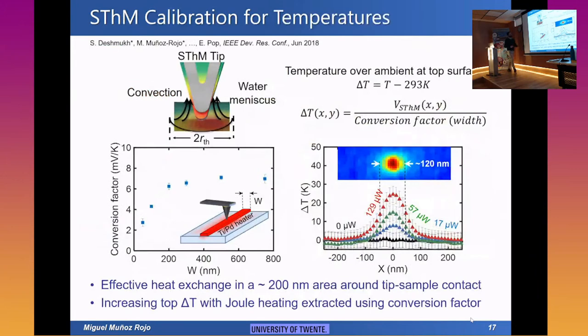This is what we observe: above a certain width, we have a very constant conversion factor from millivolts to Kelvin, but below a certain value—which corresponds to the natural thermal exchange radius of the probe—we observe a drop in this conversion factor. That is key to try to quantify the temperature of the hot spots we are observing on the surface.